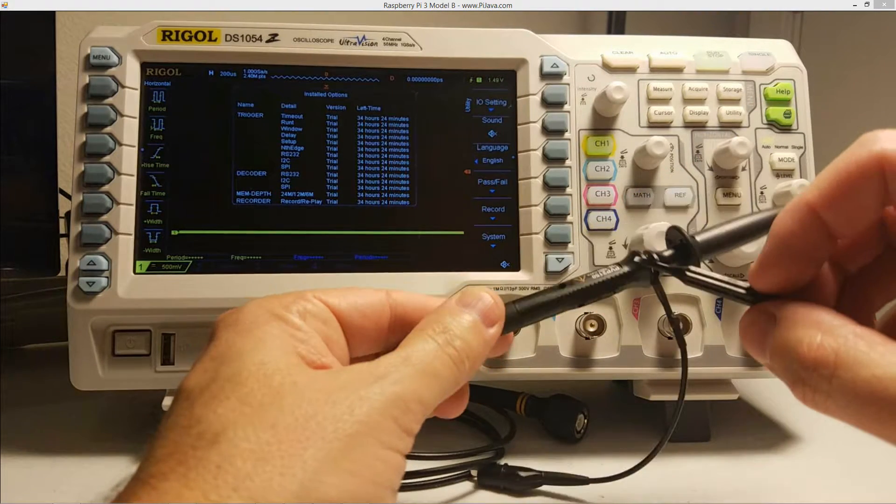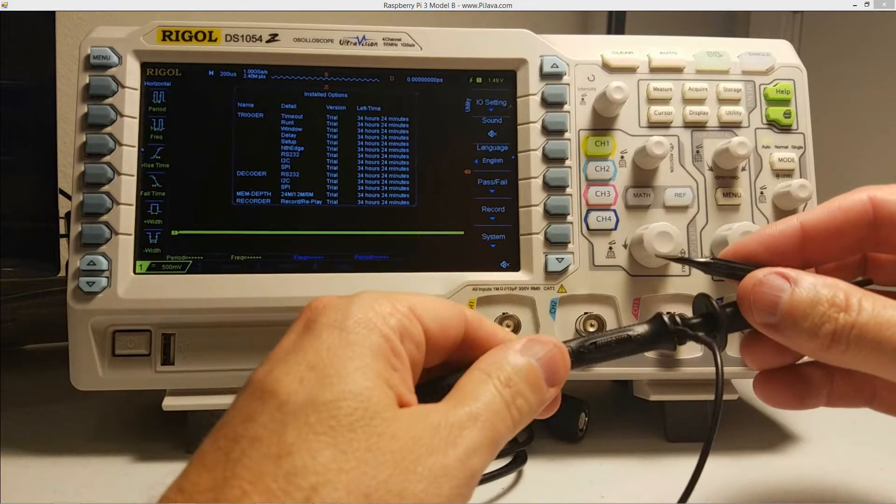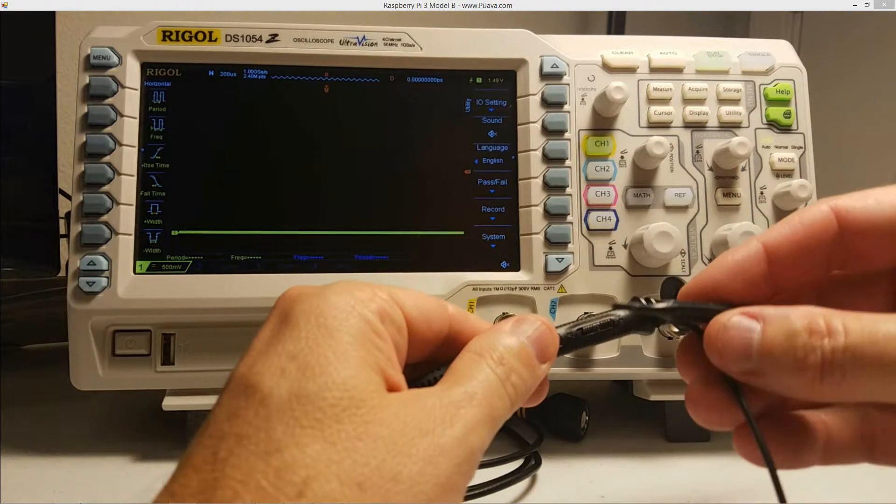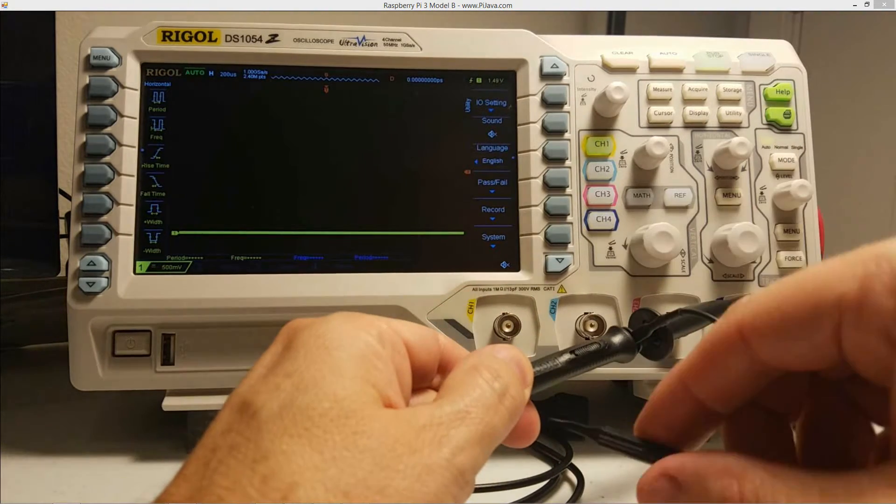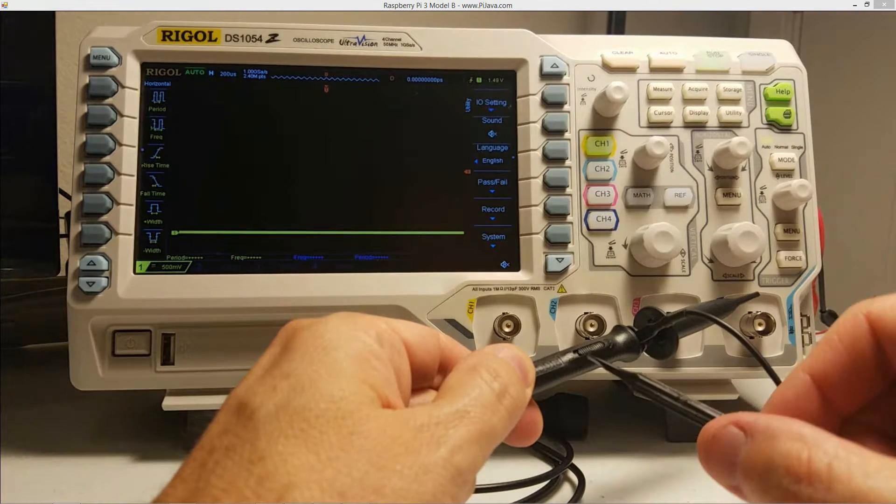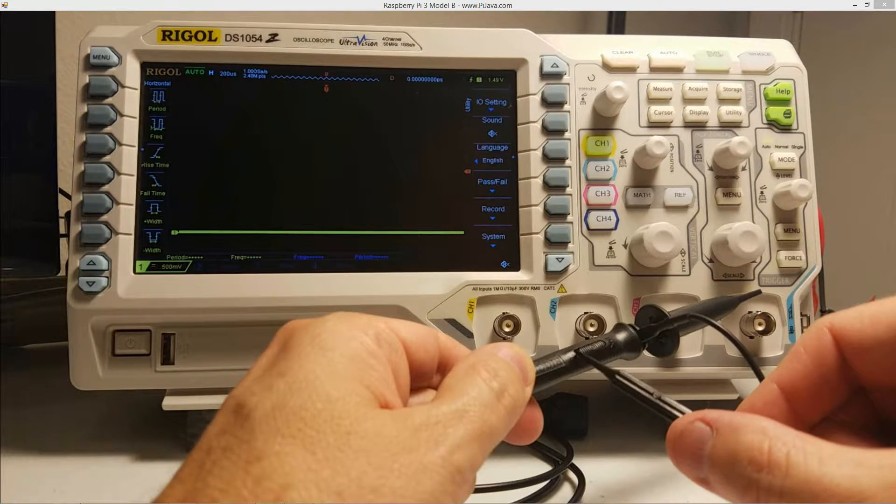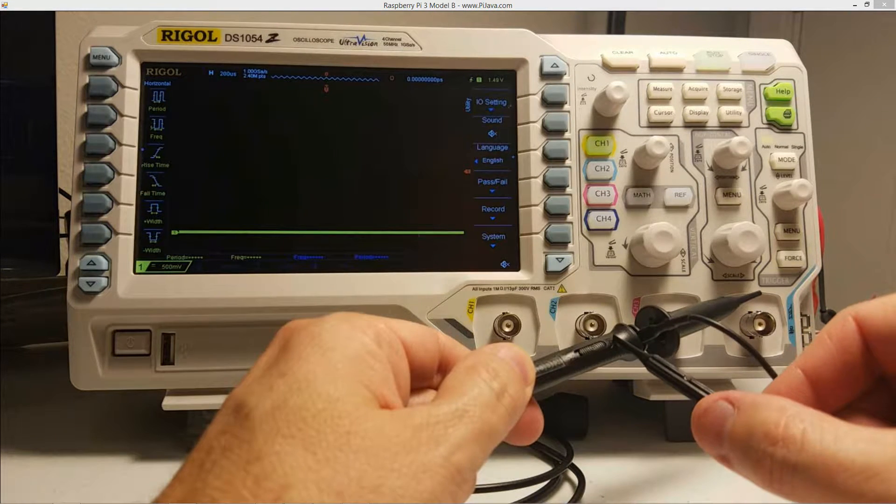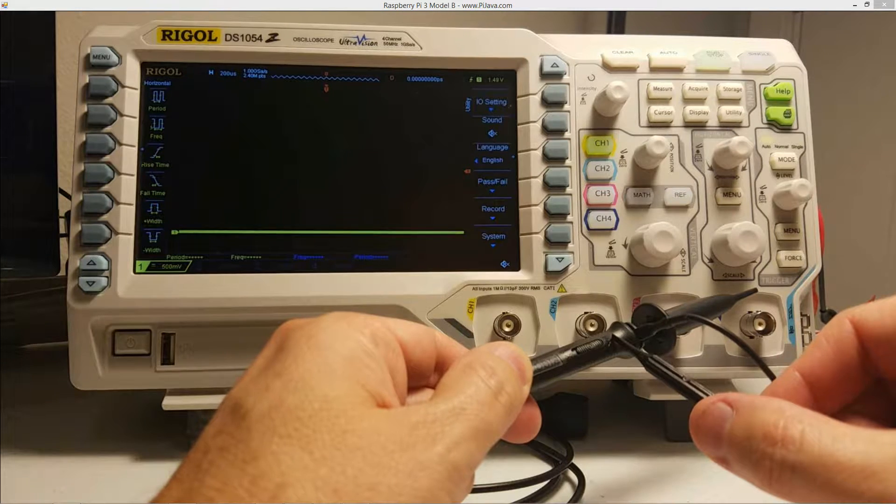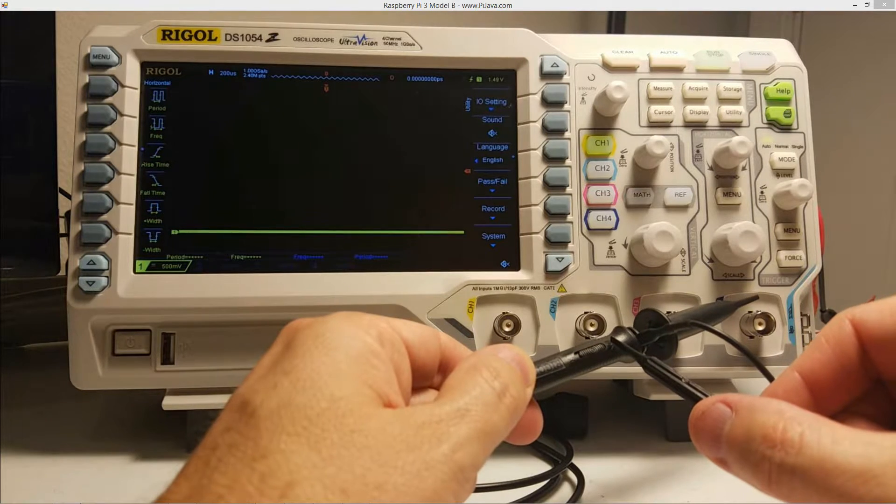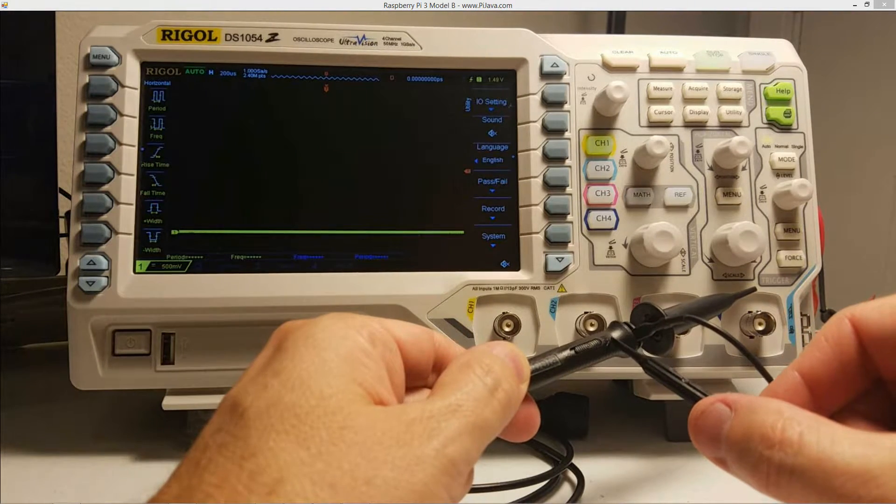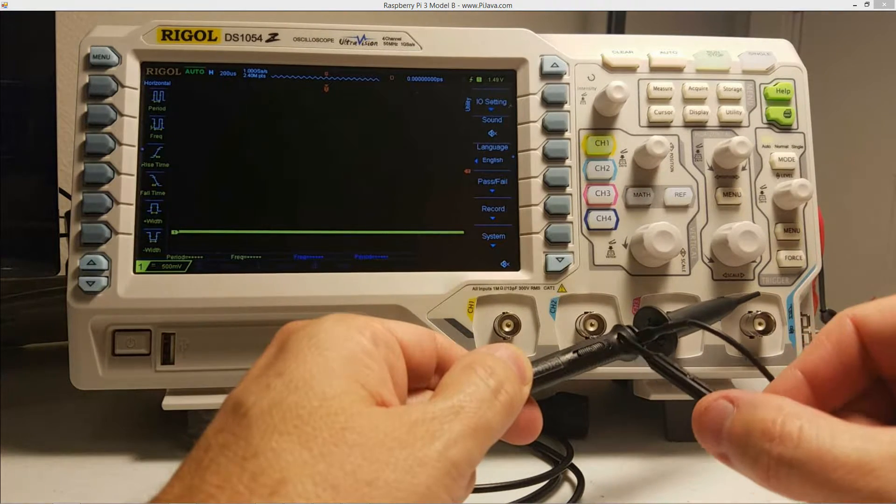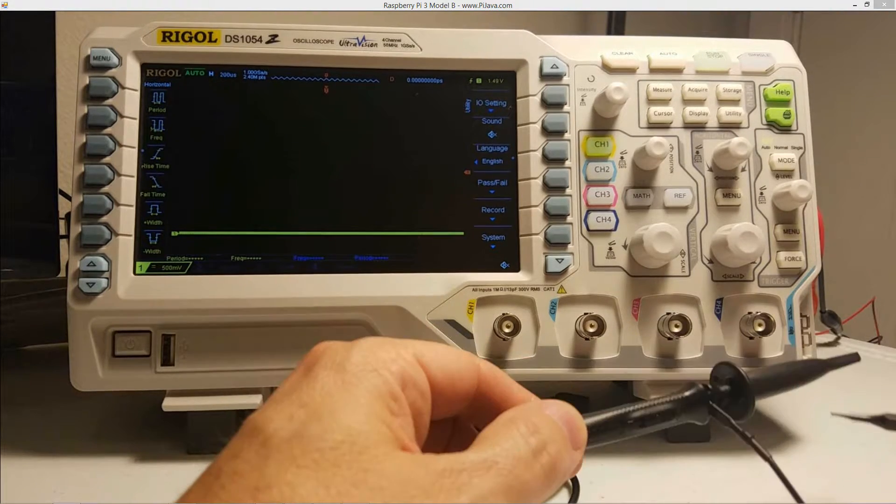Now, on the side of the probe wire here as well, we also have this little switch here, right? And we have one X down here and we have 10 X up here. That's the attenuation switch there. So we want to make sure it's set up here to 10, 10 X first.